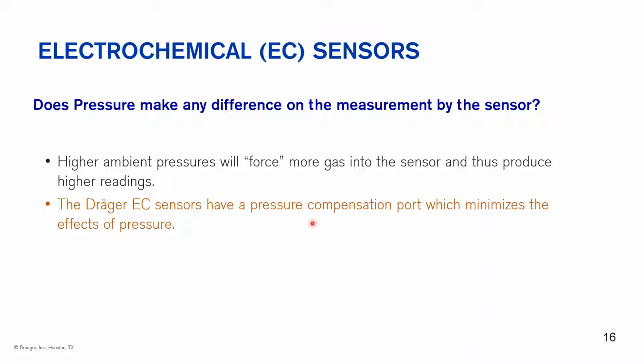I was involved in a situation with a customer going down into a mine. They were using a sensor that would go into alarm as soon as they got in the elevator and went down into the mine. And it took 10 to 15 minutes for that sensor to stabilize once they got to the bottom. Testing our sensor in that application, we had no alarms on our instruments, and before we could open a door on the bottom, our readings were back at 20.9.